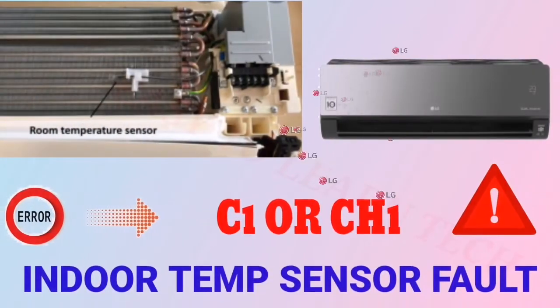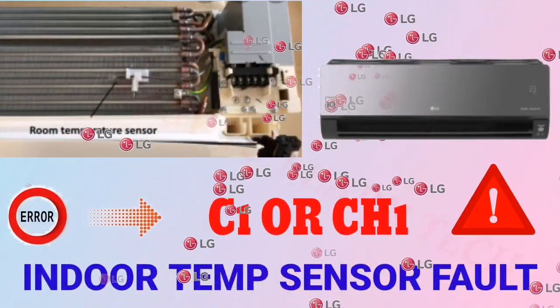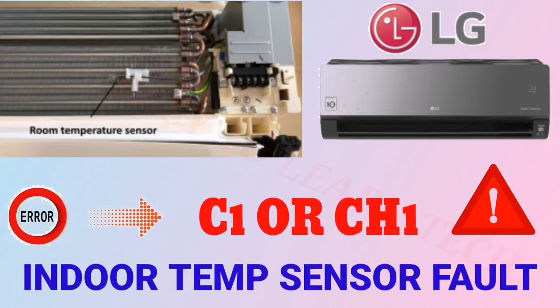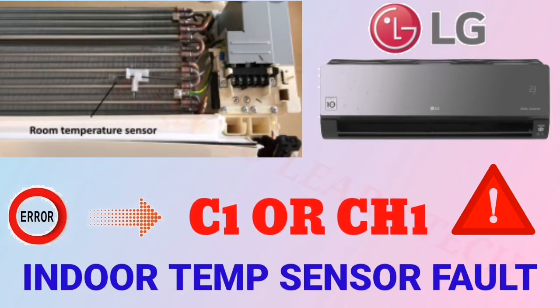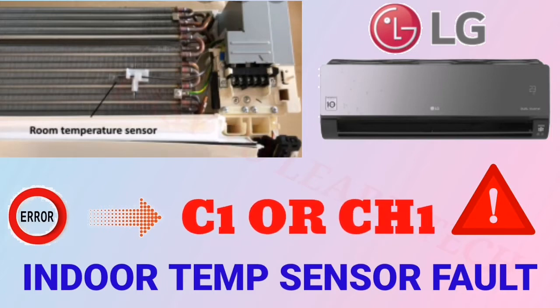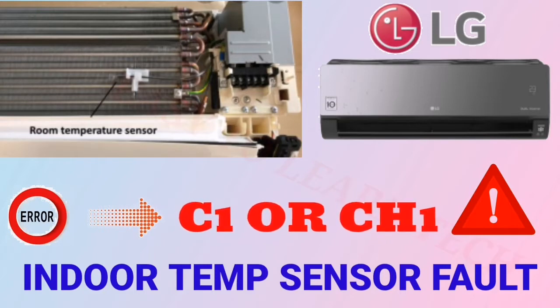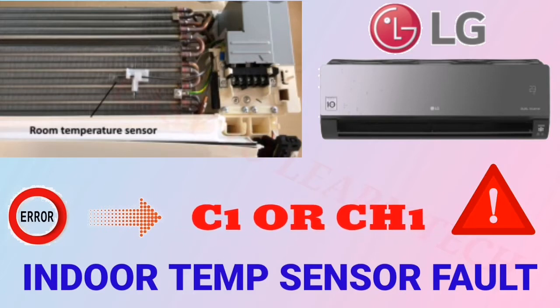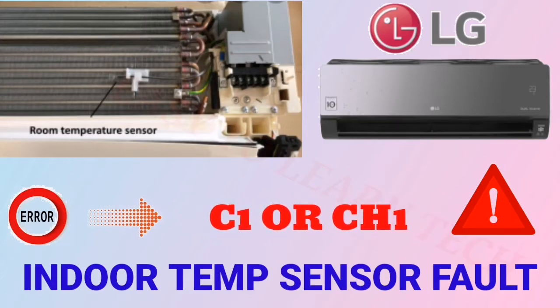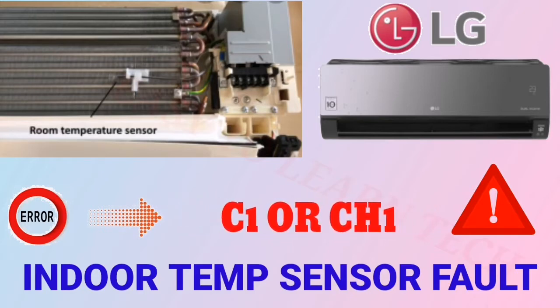When you see error C1 or CH1, it means the indoor temperature sensor is faulty. First of all, you have to check your indoor sensor, which is attached just in front of our coil with a black wire and black insulation. That is called the indoor temperature sensor. When you find this error, you have to check whether the indoor sensor resistance is perfect or not. If the resistance is not perfect, then you have to change the sensor. If the resistance is perfect and you are getting the proper resistance, and again it is showing the same error, then you have to change the indoor PCB and your unit will be in working condition.